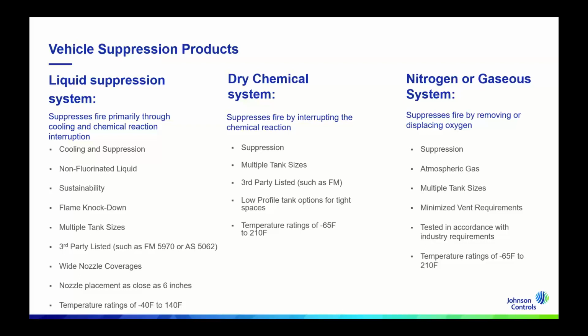It's important in liquid suppression systems today to look for a non-fluorinated liquid agent. How does that system or the agent affect sustainability ratings, the ability for the system to meet flame knockdown, have multiple different tank sizes that you can optimize, the agent quantity that would be needed on the equipment, have third-party listings, wide nozzle coverage areas, and being able to get nozzles in tight spaces, so maybe even as close to 6 inches. Another key important thing to look for in liquid suppression systems is getting down into the freeze protection range in the temperature rating.